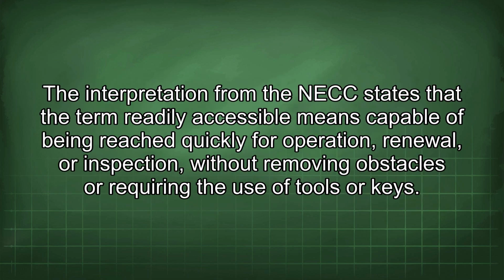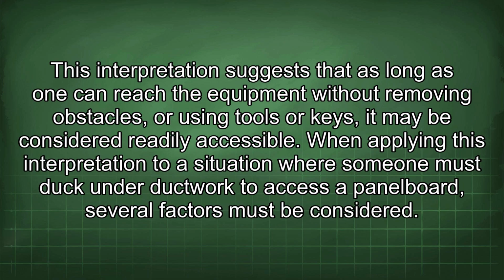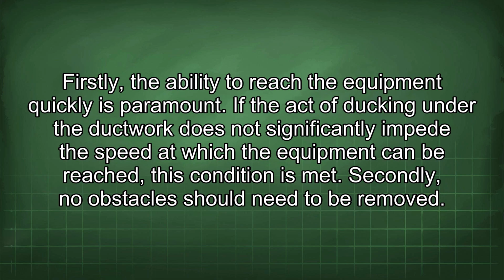The interpretation from the NEC states that the term readily accessible means capable of being reached quickly for operation, renewal, or inspection, without removing obstacles or requiring the use of tools or keys. This interpretation suggests that as long as one can reach the equipment without removing obstacles or using tools or keys, it may be considered readily accessible. When applying this interpretation to a situation where someone must duck under ductwork to access a panel board, several factors must be considered. Firstly, the ability to reach the equipment quickly is paramount.